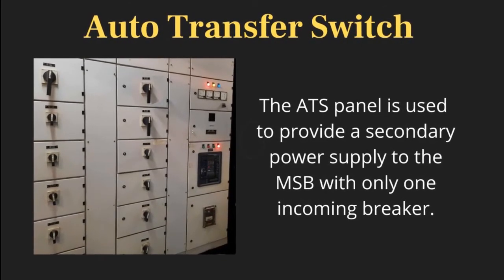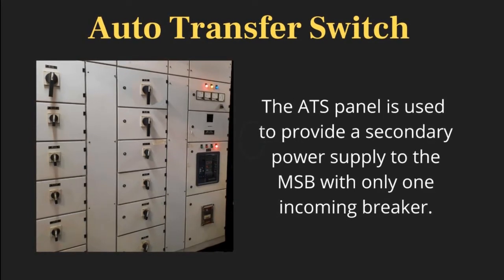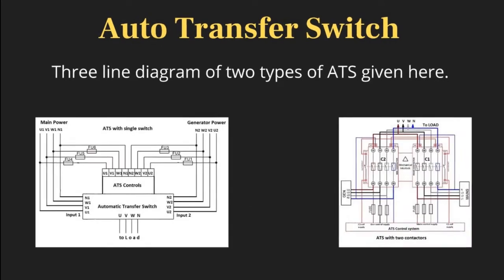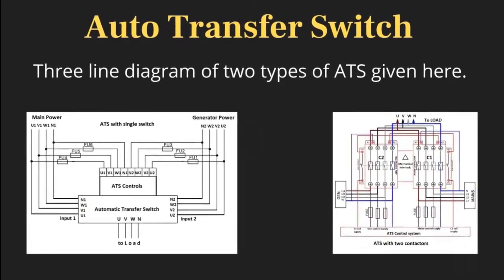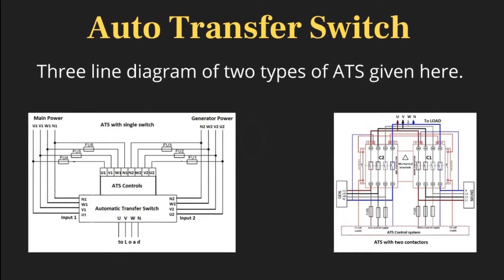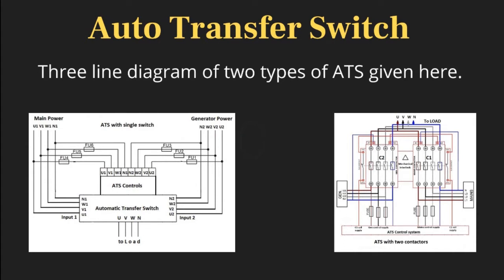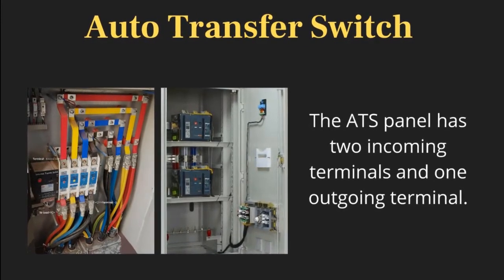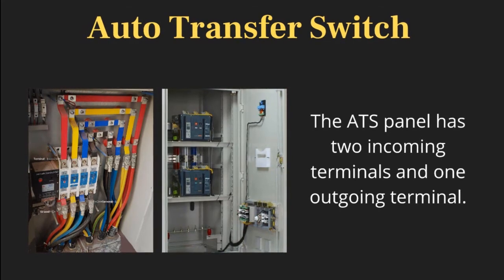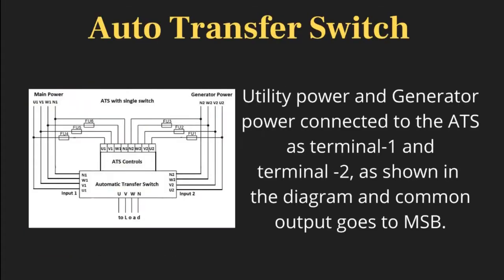The ATS panel is used to provide a secondary power supply to the MSB with only one incoming breaker. A three-line diagram and pictures of two types of ATS are given here. The ATS panel has two incoming terminals and one outgoing terminal. Utility power and generator power are connected to the ATS as terminal 1 and terminal 2, and the common output goes to the MSB.